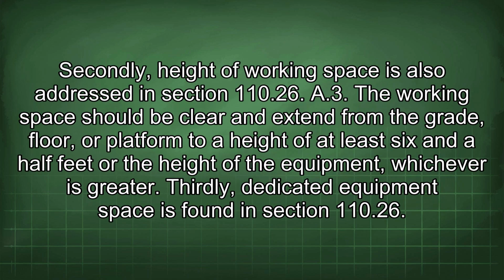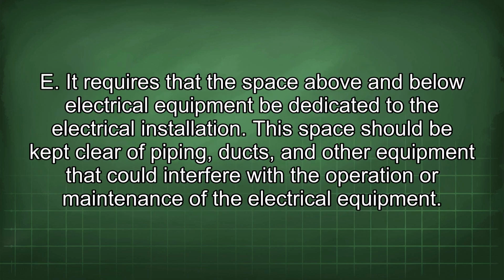Secondly, height of working space is also addressed in Section 110.26 A3. The working space should be clear and extend from the grade, floor, or platform to a height of at least 6.5 feet or the height of the equipment, whichever is greater. Thirdly, dedicated equipment space is found in Section 110.26. It requires that the space above and below electrical equipment be dedicated to the electrical installation.